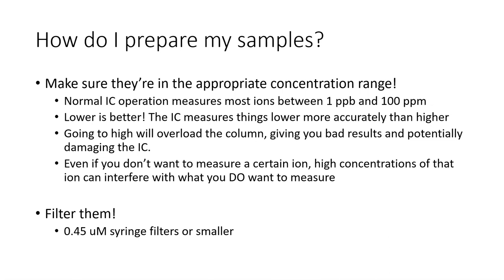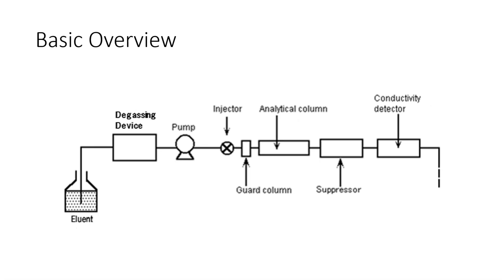Now we'll move into a basic overview on the IC. I'm going to refer to this image a lot because it goes through the general flow path, and we'll run through each one of these parts individually. We have our eluent which goes through a degasser, the pumps that push eluent through the system, an injector, a guard column and analytical column, a suppressor, and a conductivity detector.